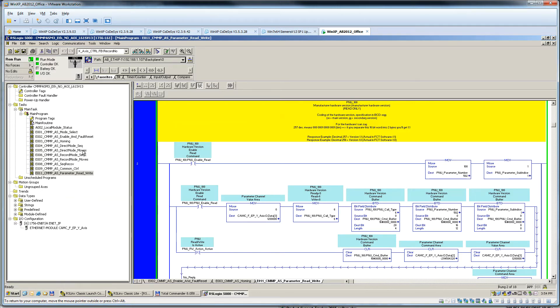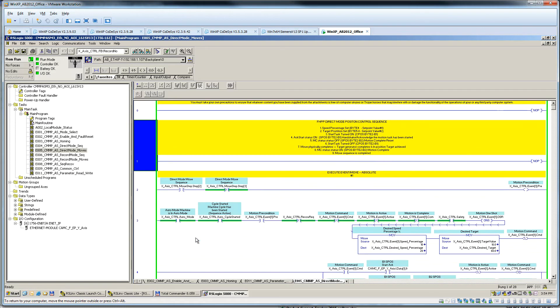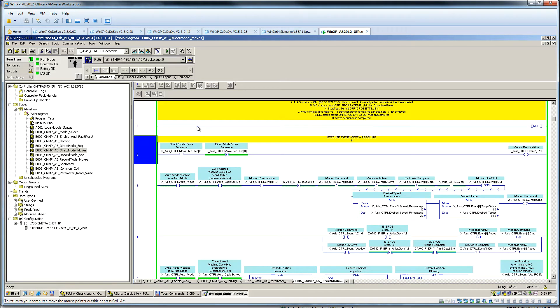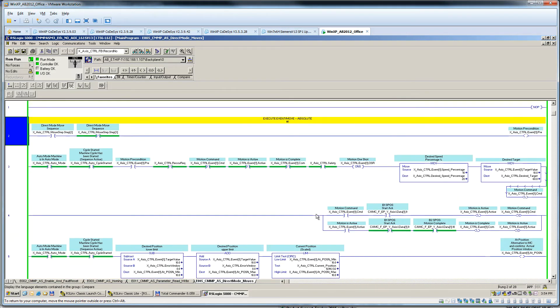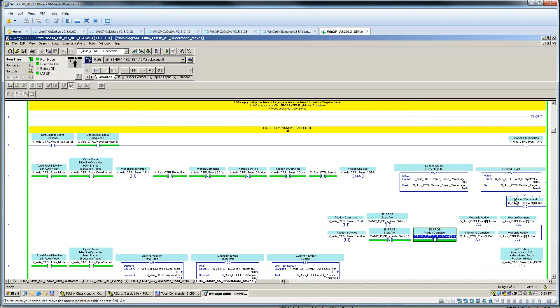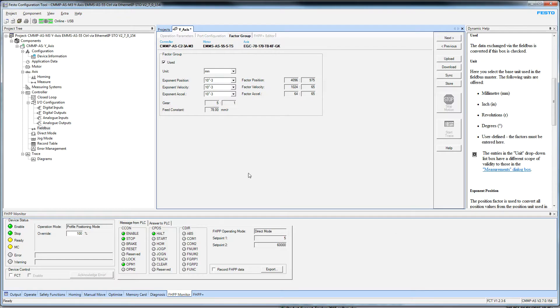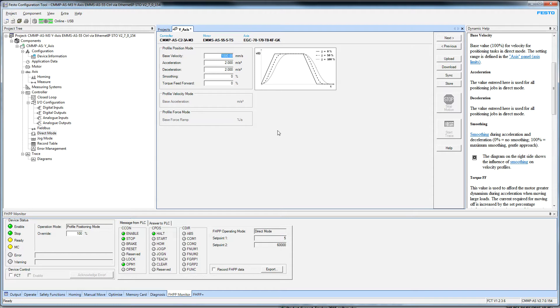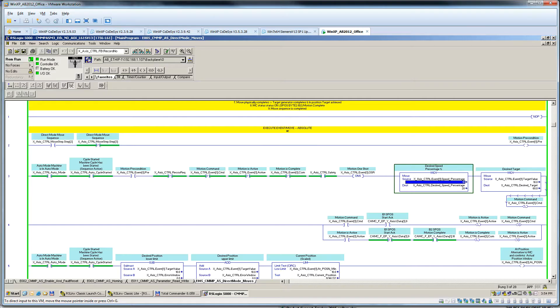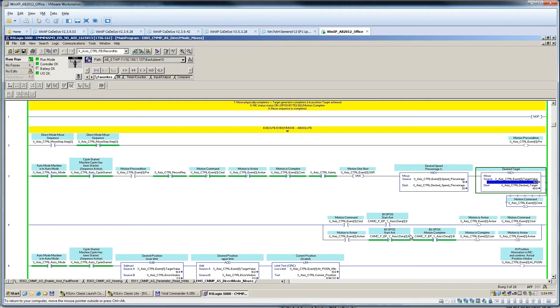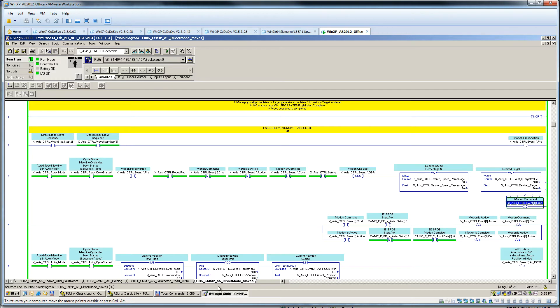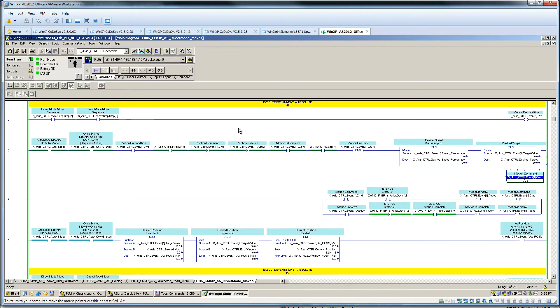There is a way to read parameters. I have not tested this yet. This is theoretical code. Hopefully I have some time to test this later. What I have working right now are the moves. In my move data, I have some common moves. The idea is that I shove a percentage into the velocity. That velocity percentage is based upon 1,000. If I put in 10%, 10% of 1,000 is 100. Then the target value gets scaled and shoved out the door into a double integer. The way the whole move works is that you start the move by turning on the start bit, wait for an acknowledge bit, turn off the start bit, then wait for the motion to complete.